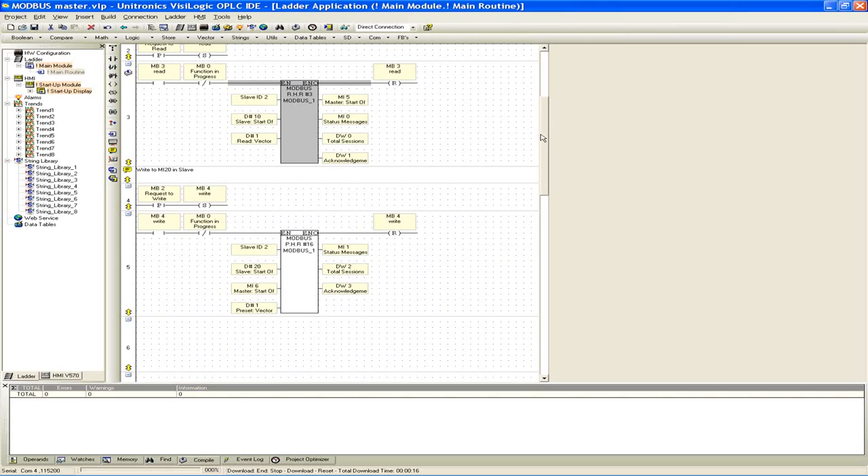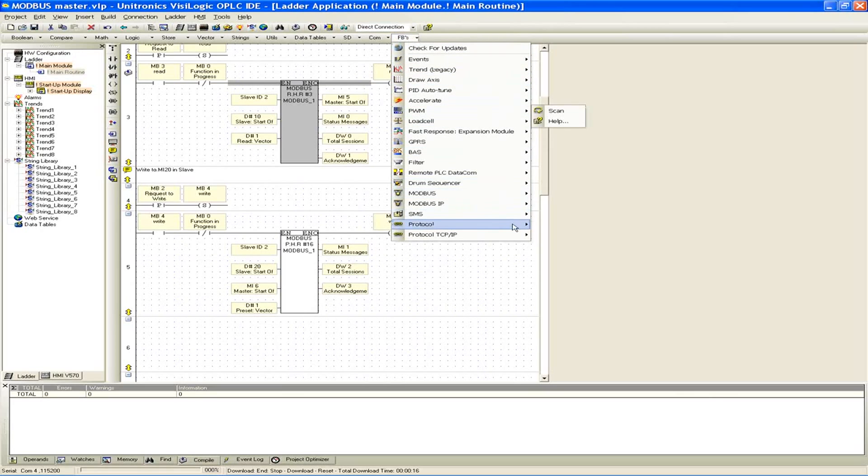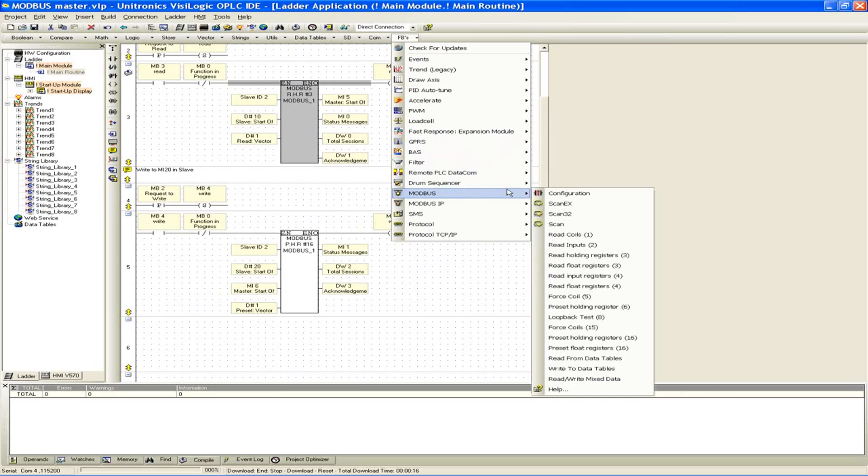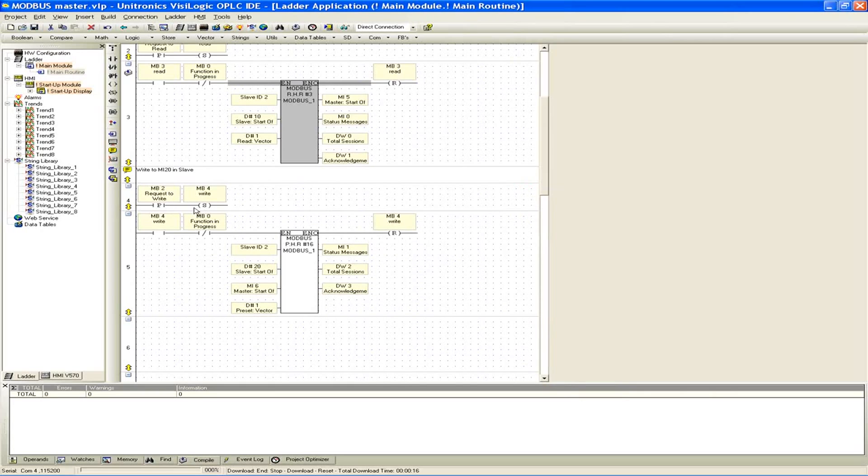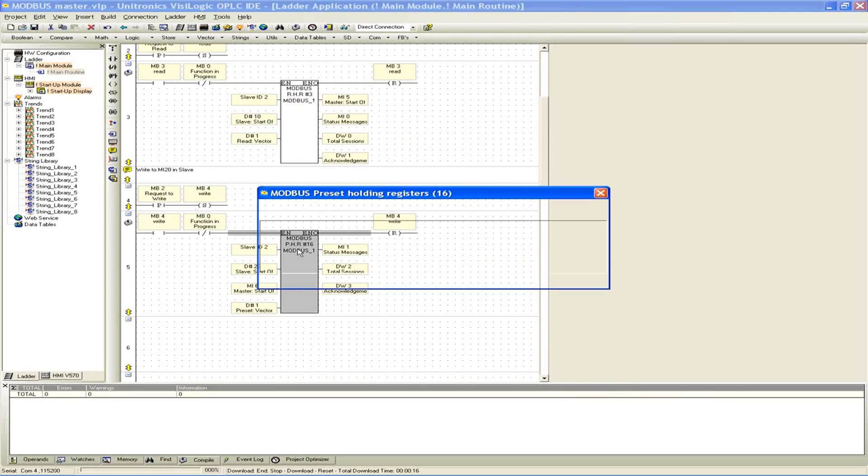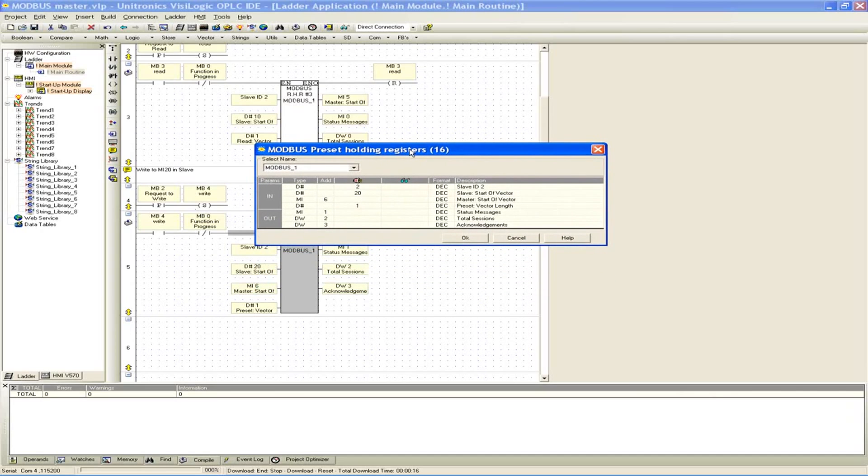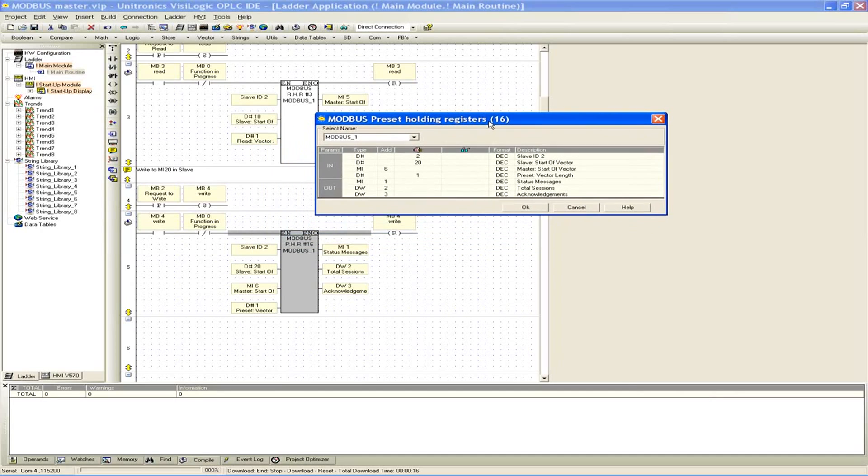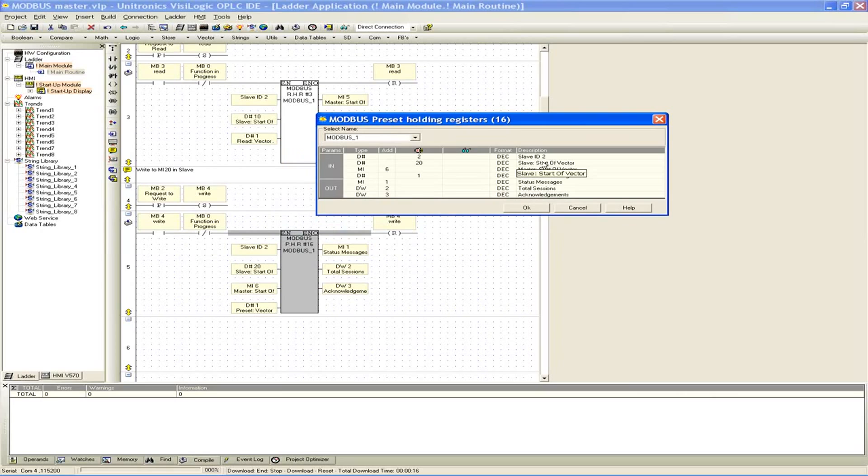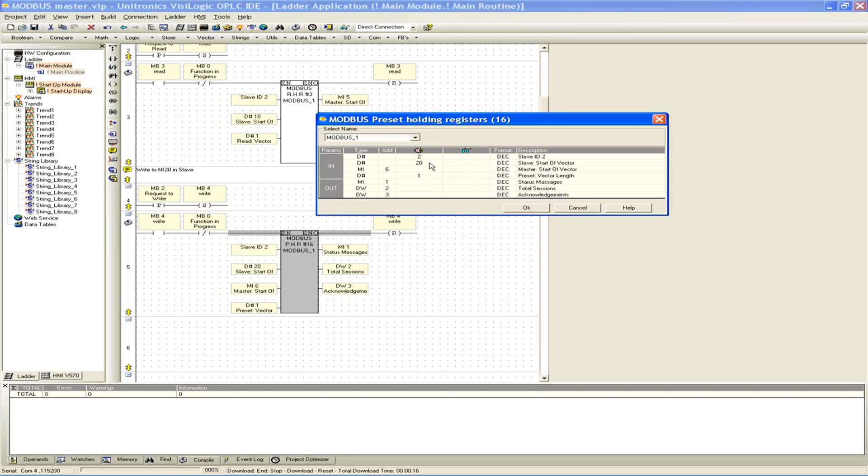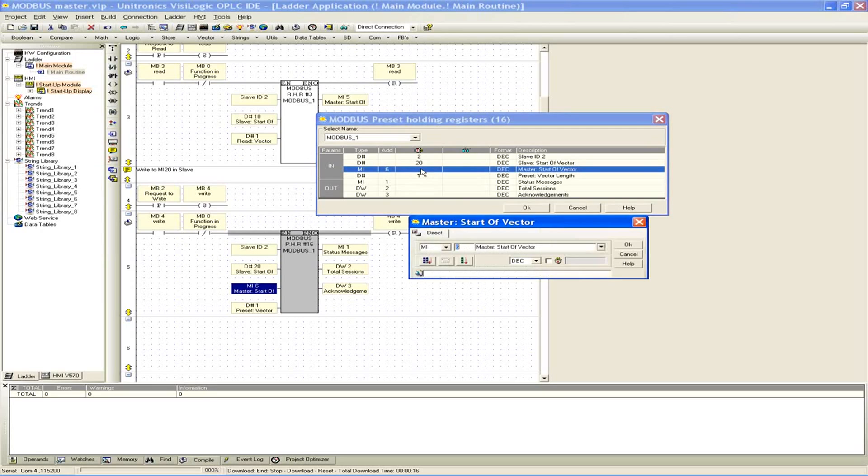And you can see we have pretty much the same setup in Nets 4 and 5 for our write. Instead here, we're using a Modbus command number 16, our preset holding register grabbed from the Modbus menu. We have our same set hold routine in our 2NET structure. And if I open this up, you'll see again it's almost identical. You need to specify your slave address, so we want you to go out and write to our slave ID number 2 on the Modbus network. Our start of vector, address 20, again which correlates to MI20. So you just enter in the Modbus number for the address that you want to be able to read. In this case we're reading 20.